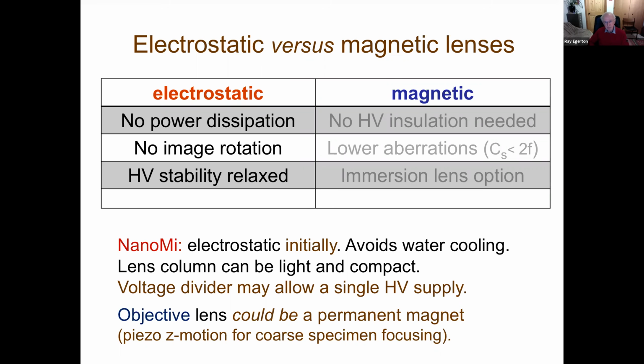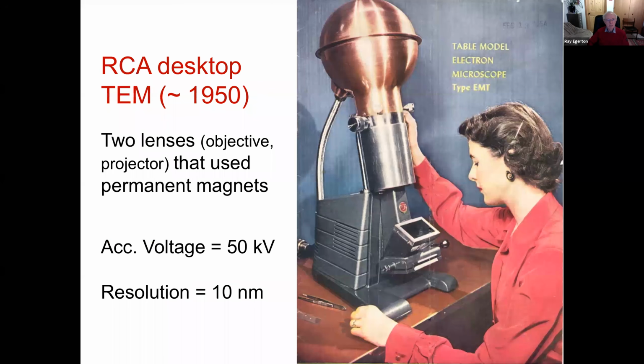Now, if we wanted a better resolution, then sometime in the future there is the option that we could have a magnetic objective lens, but with a permanent magnet, again avoiding the need for water cooling. And there are precedents for having a permanent magnet objective lens. In fact, there was a machine marketed by RCA around 1950, marketed as a desktop electron microscope with just 2 lenses, and both of those lenses used permanent magnets. The accelerating voltage apparently was as high as 50 kV, and the resolution claimed was 10 nanometers.